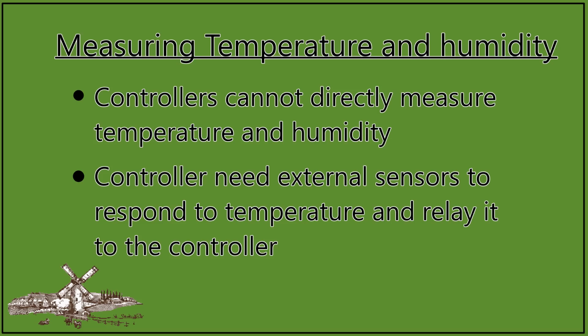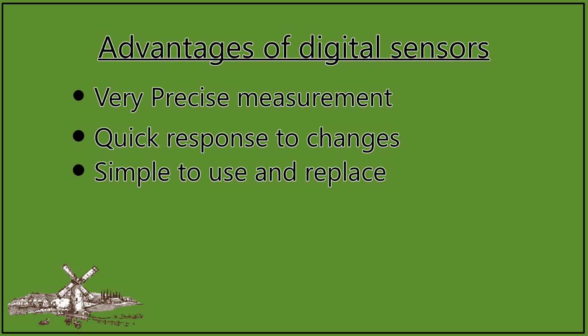Now, the thing we need to realize is that our controller cannot measure temperature, nor can it measure humidity. So in order for us to control the temperature and the humidity using our controller, we have to first attach a sensor. And the job of the sensor is to respond to the temperature and then send a message back to the controller as to what the temperature actually is. Now, the advantage of our sensors are that they are very easy to interface with our controllers. Very, very simple. On the other hand, they are also very precise.